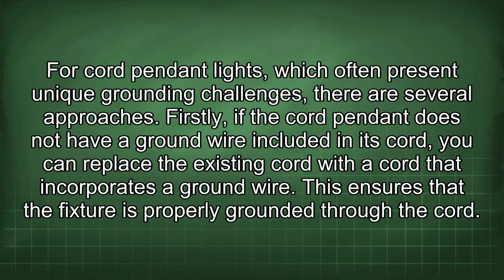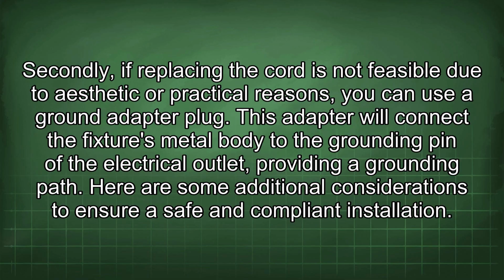For cord pendant lights, which often present unique grounding challenges, there are several approaches. Firstly, if the cord pendant does not have a ground wire included in its cord, you can replace the existing cord with a cord that incorporates a ground wire. This ensures that the fixture is properly grounded through the cord. Secondly, if replacing the cord is not feasible due to aesthetic or practical reasons, you can use a ground adapter plug. This adapter will connect the fixture's metal body to the grounding pin of the electrical outlet, providing a grounding path.